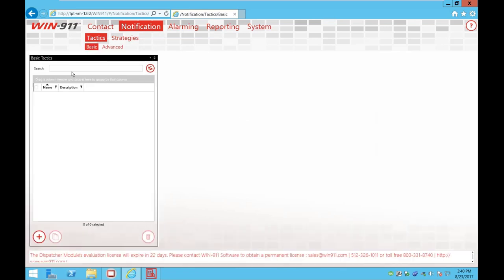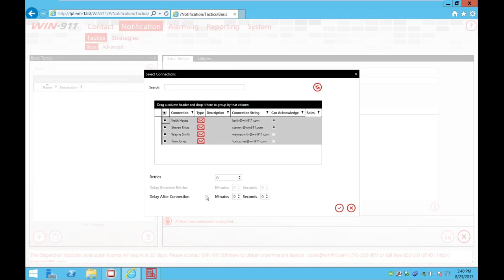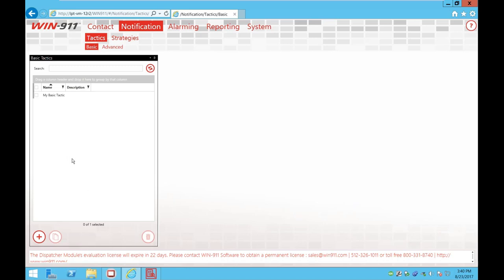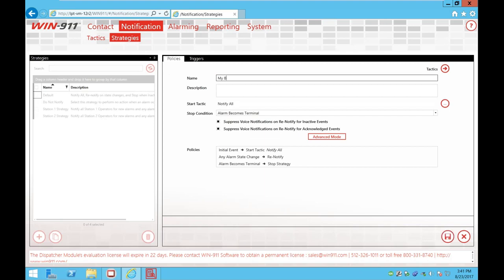I want this particular person to be able to acknowledge, so I'll go to Ack Options and allow them to acknowledge. What that means is I can reply to this email and acknowledge the alarm without typing anything — just replying acknowledges it. Once you create a connection — whether it's email, mobile, SMS, or voice — you need to go to your tactics. So I'll go to Notification, then Tactics. I want to make a basic tactic, so I'll hit the plus button to create a new one, give it a name — I'll call this my basic tactic. I'll hit the plus button, select all my email contacts, and go ahead and add them in. I can move them around depending on the order I want, and then save it. So I've created my tactics and have my call-out list.